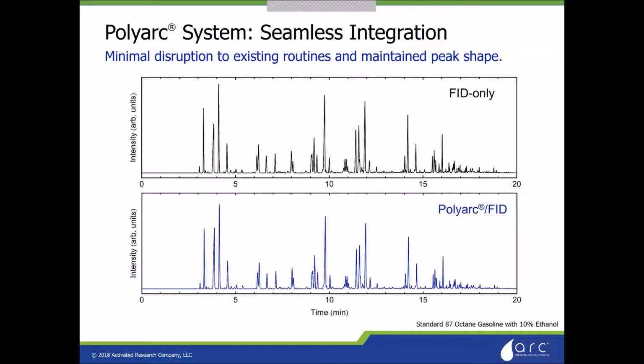If you get below a 0.25, we have products coming out soon that will help with fast GC applications and even sharper peaks. But the Polyarc itself will work well with 0.25 and 0.32, as well as 0.53 columns. So you can see here we have very uniform, similar peak shapes. The only big difference here is the ethanol peak, which I'm pointing out. I'm not sure if you can see. Yep. So that has actually increased in area because ethanol is really the only oxygenate in the sample. So that increases because we're converting it to methane, and it burns more efficiently as methane.